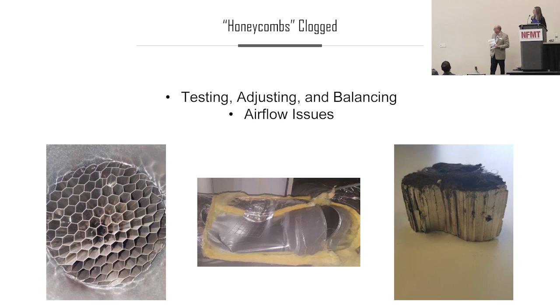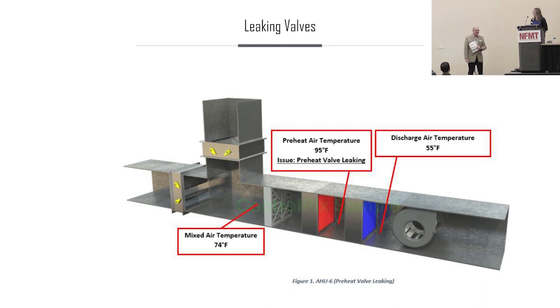Another note on this slide: if you have occupant complaints about too much airflow in a space, try not to crimp the ductwork to reduce those airflows. They do make dampers that can do that for you. In all fairness, a facilities guy is not the one who crimped the ductwork in lieu of a damper. That was a faculty member who did that one.